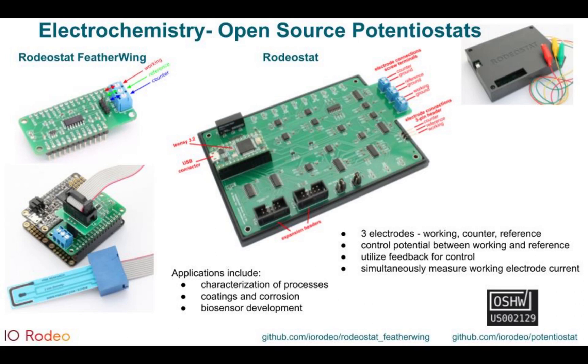These are typically not passive instruments. You may on some occasions hold the voltage between the working and reference electrodes constant, but in many more cases you're varying it according to some desired waveform — sweeping the output through a ramp, cycles, or pulses. The changes in the current tell you a lot about the electrochemical processes occurring on the electrodes, allowing you to characterize things like reductive potentials or the reversibility of reactions.